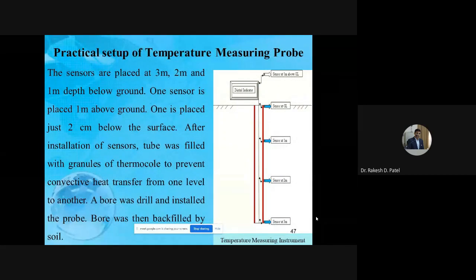This is the practical setup of the temperature measuring probe. The sensors are placed at 3-meter, 2-meter, and 1-meter depth below the ground, and one sensor is placed 1 meter above the ground for measuring the atmospheric temperature throughout the year. And one is placed just 1 or 2 centimeters below the surface for measuring the surface temperature of the ground.